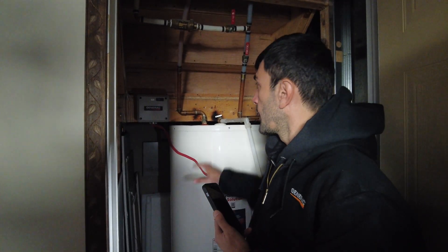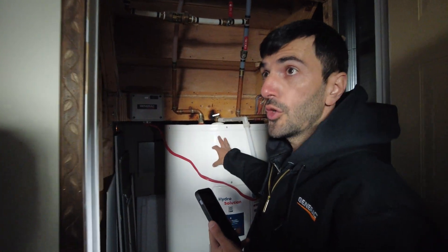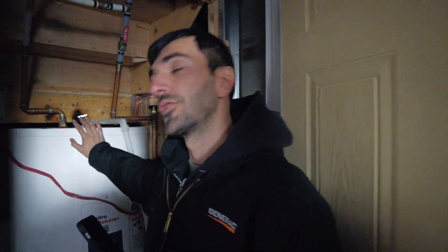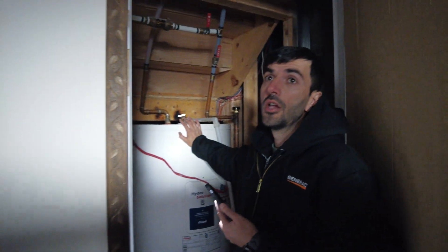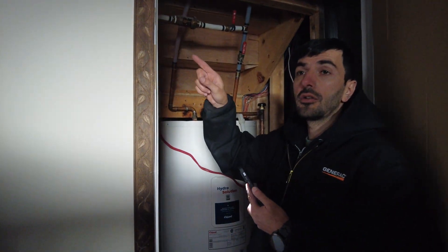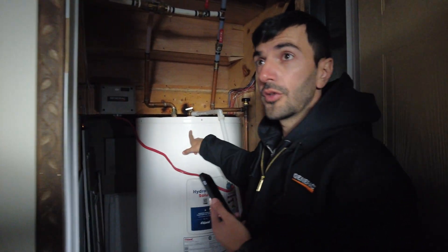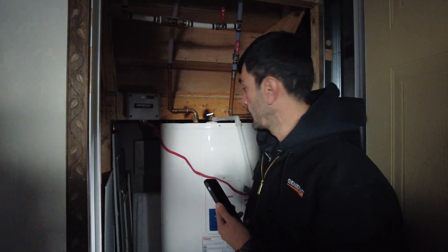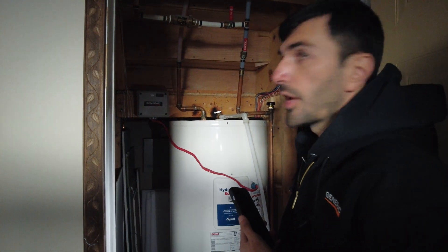After 30 minutes it's going to try again. If it's still overloading, it's going to keep those loads off until hydro comes back. So it tries two times and then it stops. If you want to reset it, you can turn the breaker for the hot water tank off and on, and it's going to do the same cycle two more times.